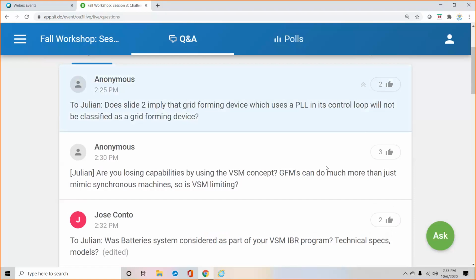Yeah, that was a key part of our initial research, because originally back in 2013 we didn't think that VSM and grid forming, as it was defined then, about 7 years ago, would be suitable for the GB system. But the technology has progressed and we've moved away from having a PLL. We feel that for the GB system, moving away from PLL does mean it can be a grid forming device, and therefore with the PLL in the control loop it will not be classified as grid forming here in Britain.